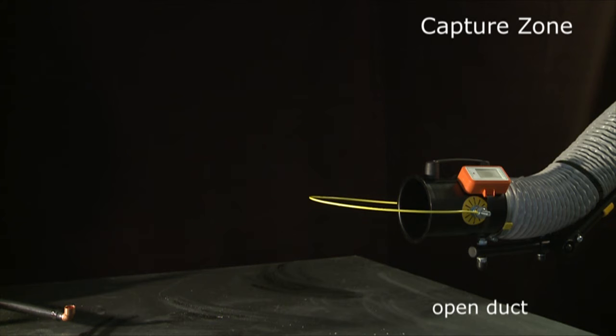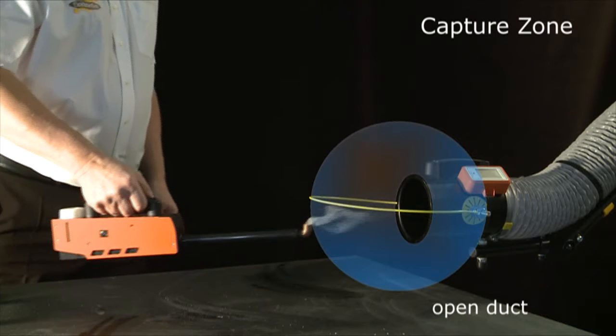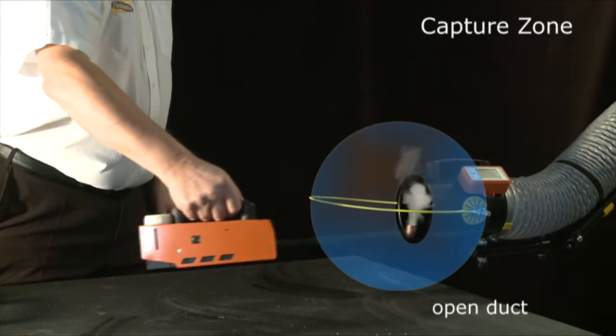The capture zone is the space in front of the hood where the air velocity is sufficient to capture the contaminant cloud. One way to envisage it is as a bubble in front of the hood. Inside the capture zone, almost all the contaminant will be captured.